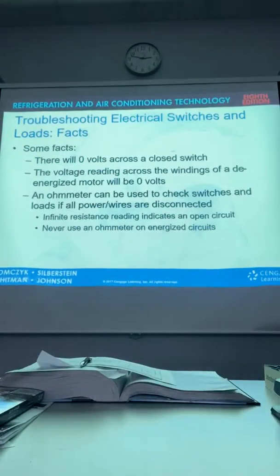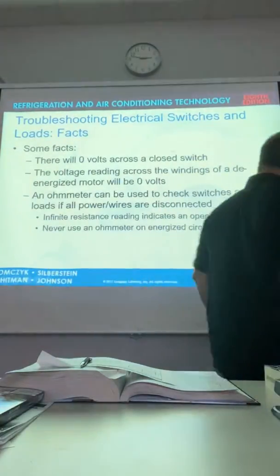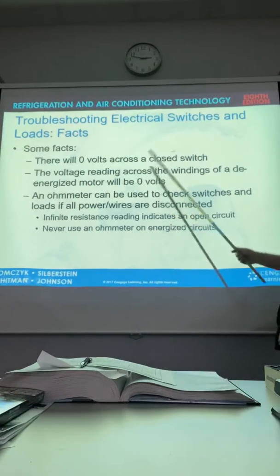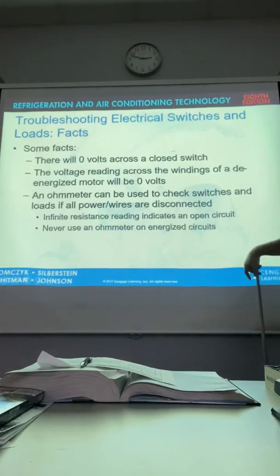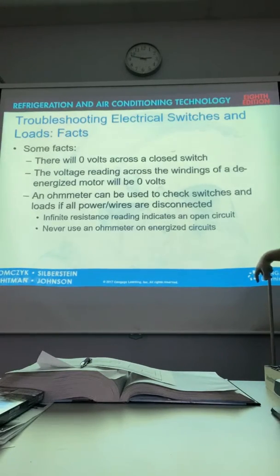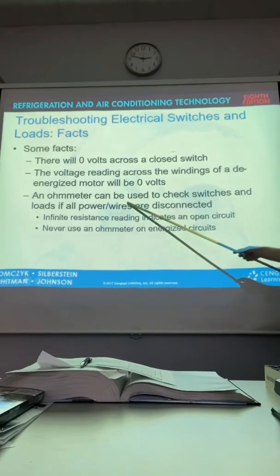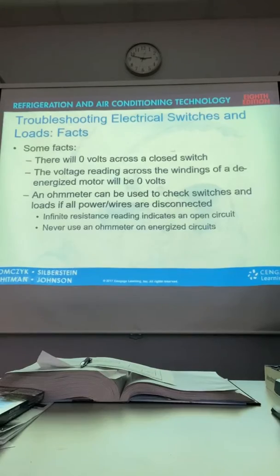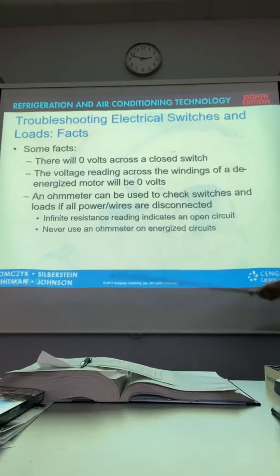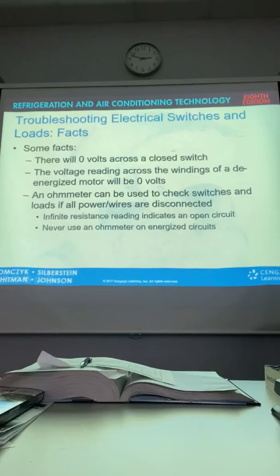Okay, so we're gonna pick up right where we left off the last time. And I want you to remember some facts real quick. There will be 0 volts across a closed switch. The voltage reading across the windings of a de-energized motor will be 0. An ohm meter can be used to check switches and loads if all power wires are disconnected. Do not check with an ohm meter if it's still hot with voltage. Infinite reading means it's an open circuit, and never use the ohm meter on an energized circuit.